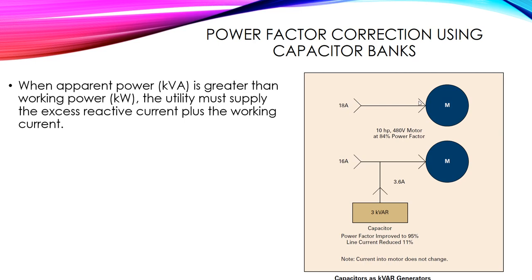Remember that the total current entering the motor is the same — 18 amperes. The current entering the motor is the sum of 3.6 and 16 amperes. Someone might ask: the total current is 18 amperes, but here we have 16 and 3.6, whose arithmetic sum is 19.6 — so why is this different from 18?